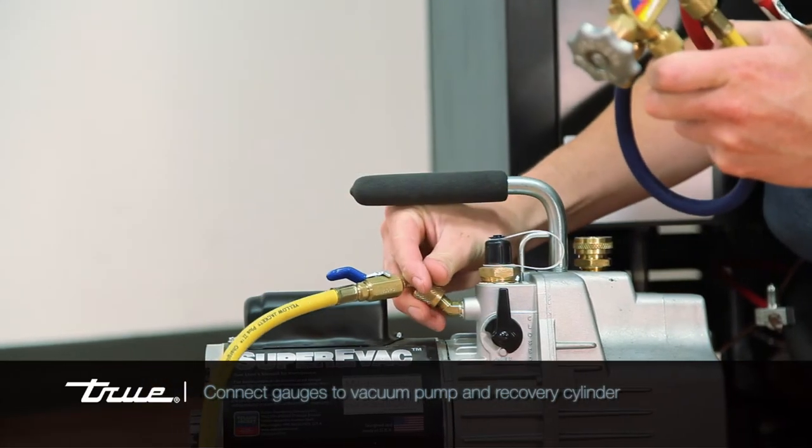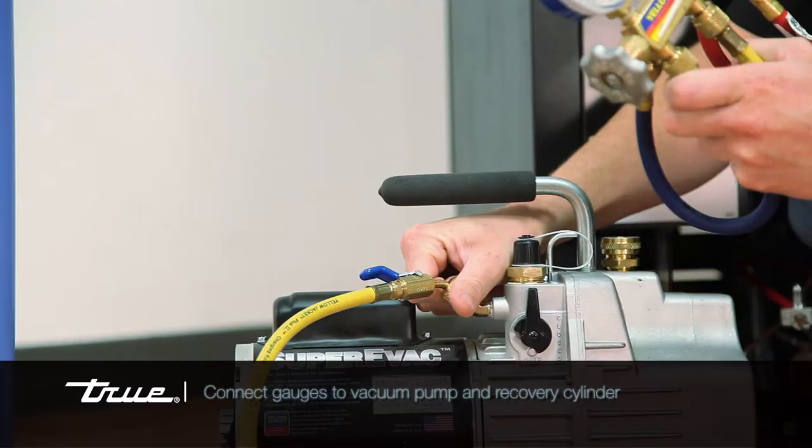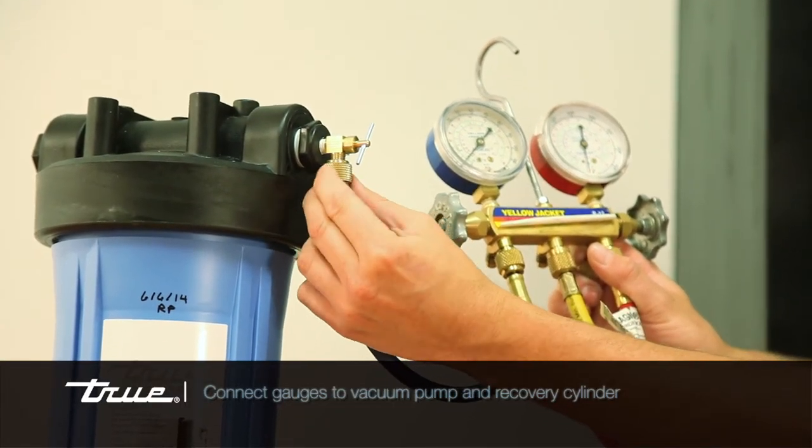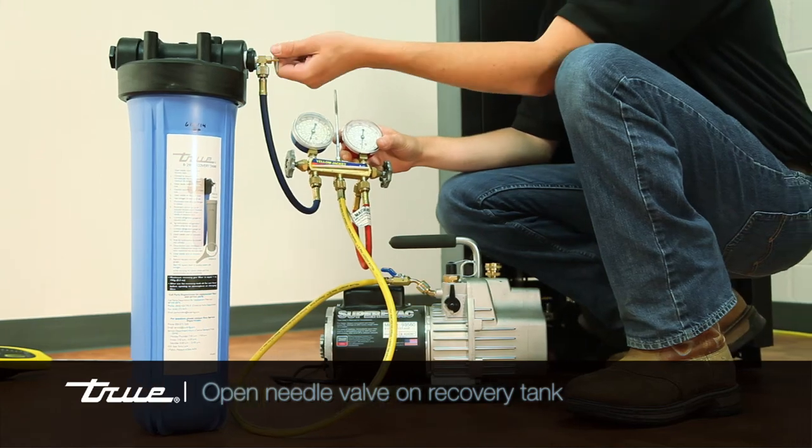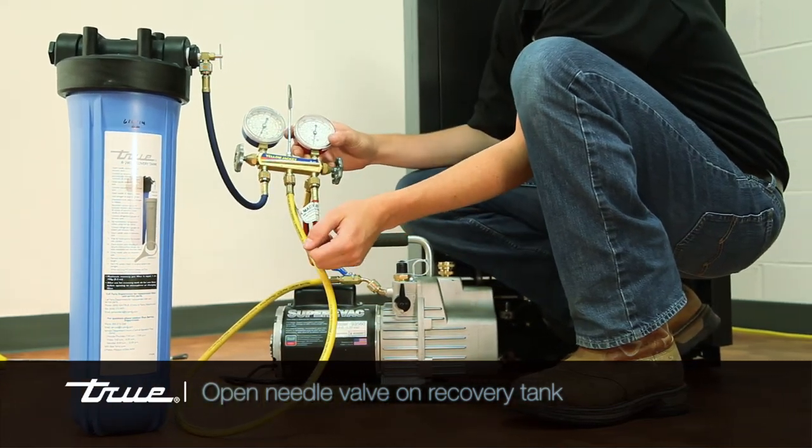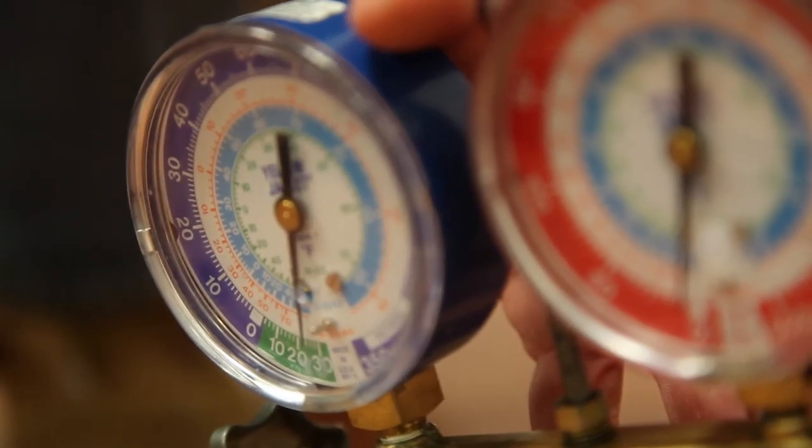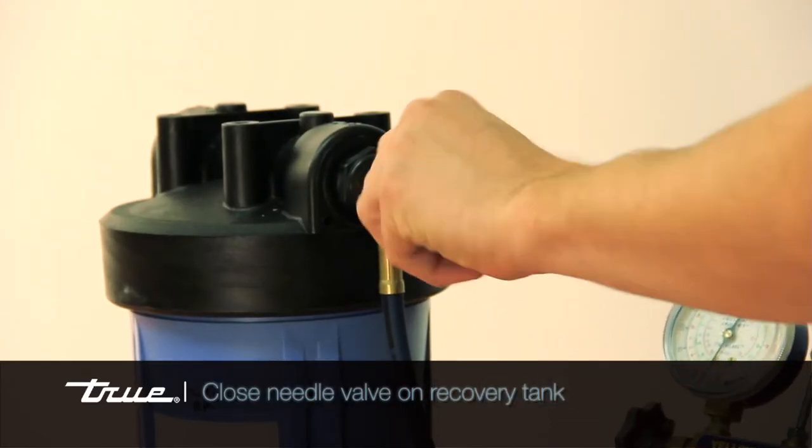Connect your refrigeration gauges to the vacuum pump and the recovery cylinder. Then open the needle valve on the top of the recovery tank and begin to evacuate the cylinder to a minimum of 25 inches of vacuum. Close the needle valve on the recovery tank.